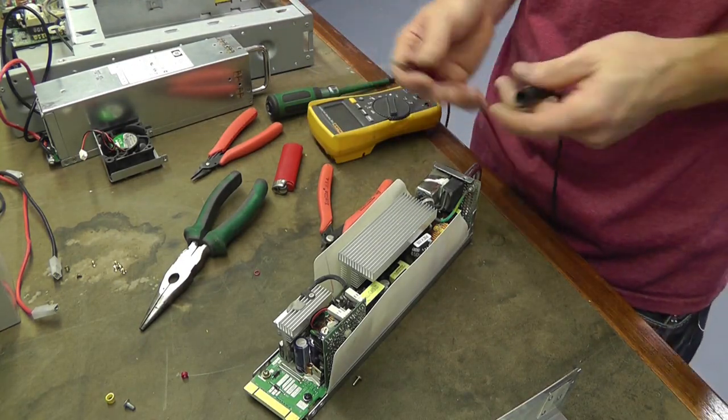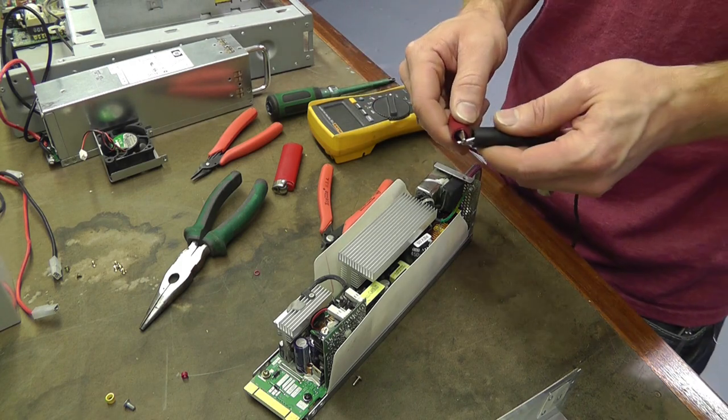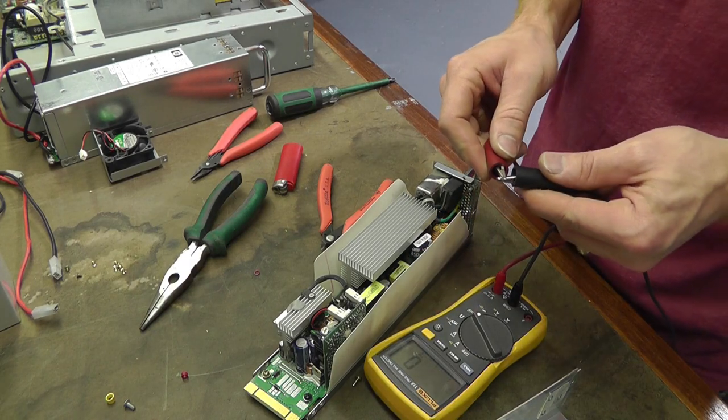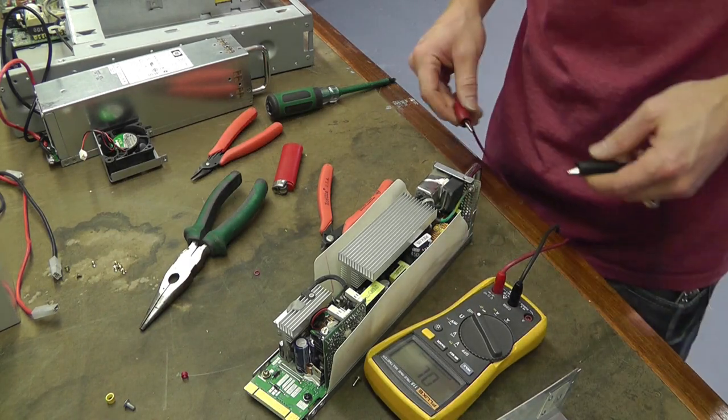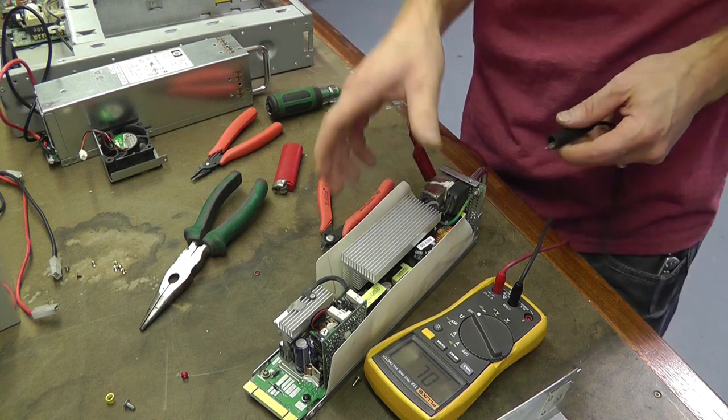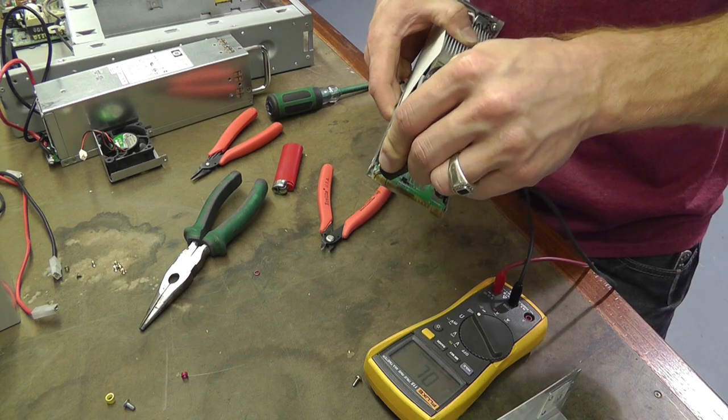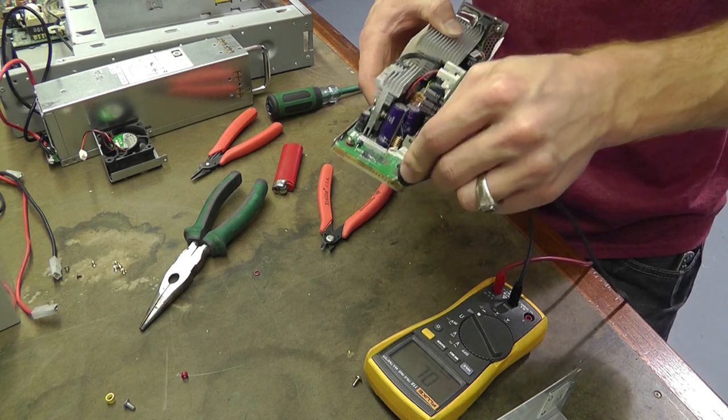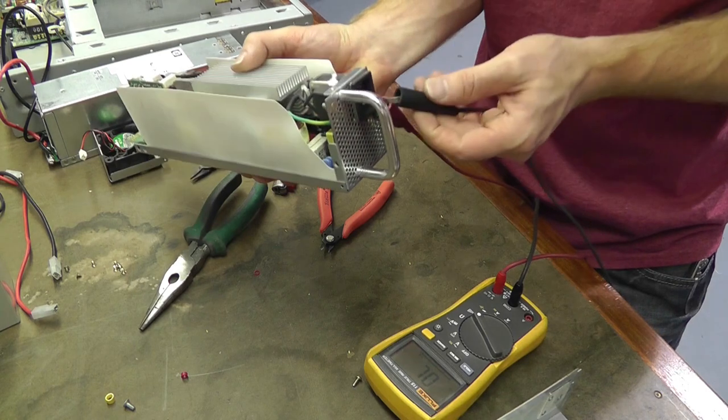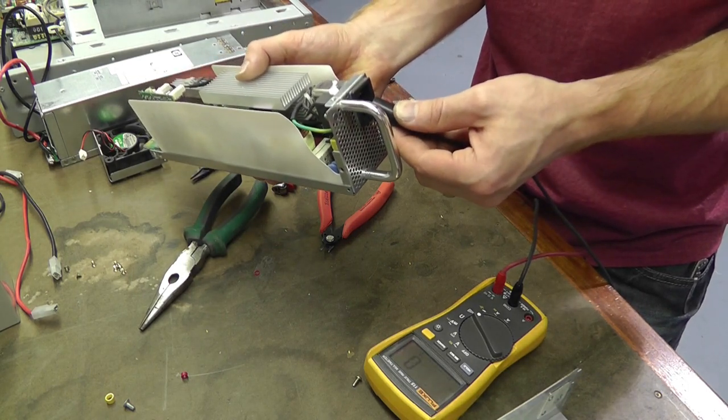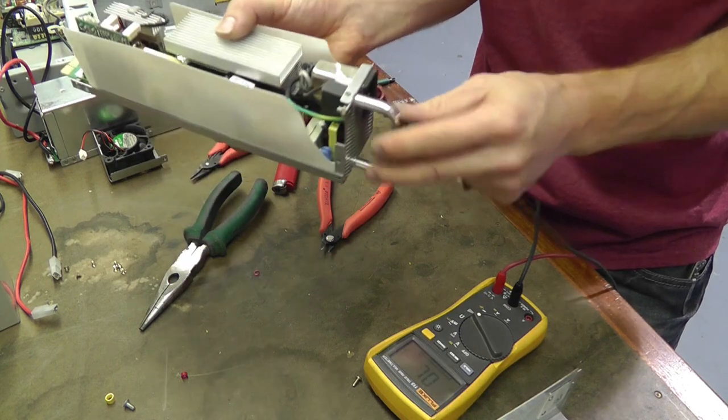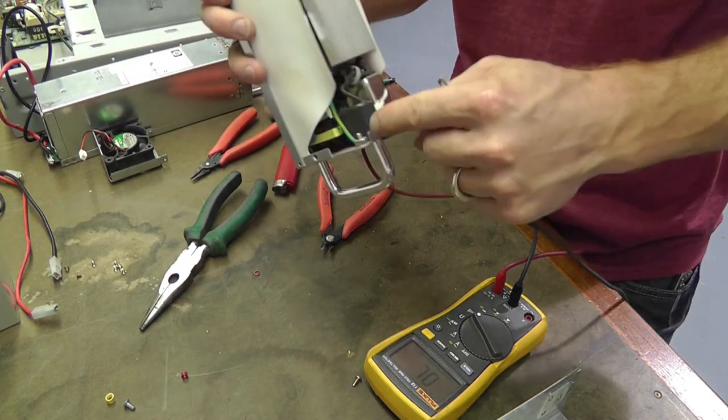Alright. So, I forgot to do the continuity test before and after. I'm going to go ahead and do the continuity test now so you can see. So, I don't know if you can hear my meter squealing. But it is. So, just, you know, check one of these to the case and test your grounds. I got complete isolation. Now, you can see if I touch my ground to my case, I still get continuity. And that's because this is still grounded and this is still grounded.